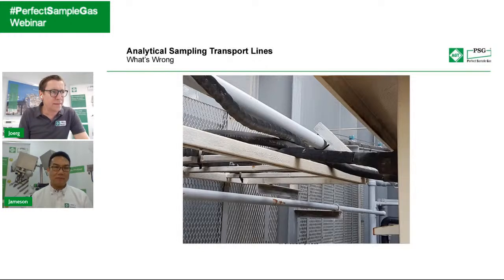But if there is some insecurity also regarding particles and the efficiency of particle filtration in the gas sampling probe, many of our customers like to use replaceable tubes inside the heated sample line. So this could also be an option. We always say up to a length of 30 meters, even installed, it is possible to change. Then you just decide to change the PTFE inside. Sometimes that can be pretty good.